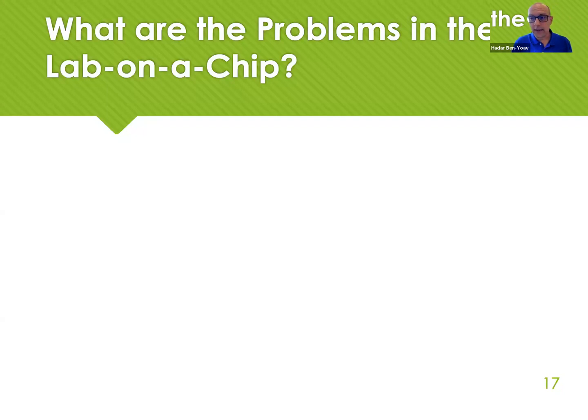For example, think about it. The binding is dependent on the humidity, the humidity percentage in the system. Different humidities are a problem. I don't know what the humidity in Xi'an is now, but the humidity in Ben Gurion is something like 20%, 30%. If you use this device here in Ben Gurion, and use the device in Xi'an, you're going to get different results because of the humidity.